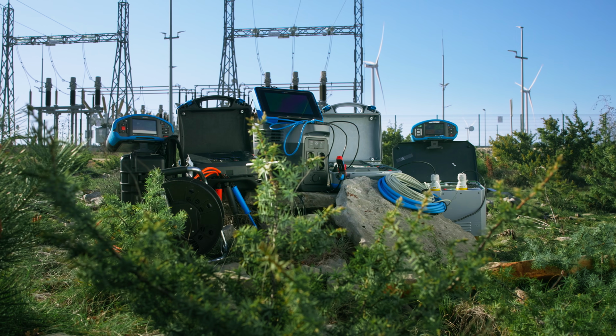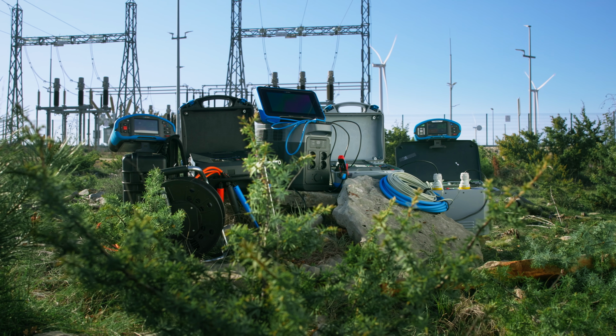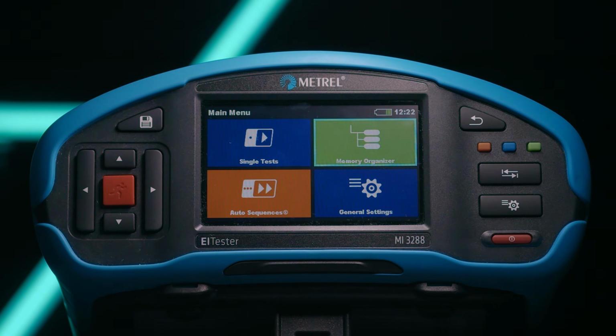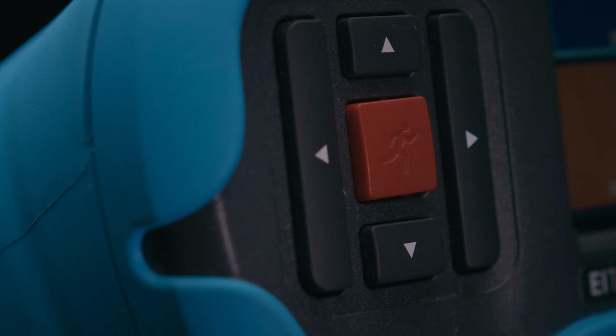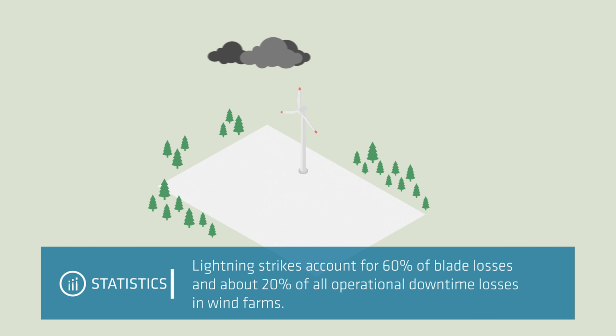In these critical tasks, Metrel's advanced and portable testers play a vital role. Instruments like the MI3288 tester are designed to perform high-precision measurements of grounding impedance, touch and step voltages, insulation resistance, and earth bonding using the 4-wire Kelvin method.